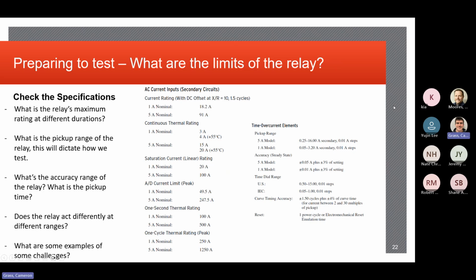Looking in the manual as well, you're going to be able to dictate what the limits of the relay are. Going back to Brian's point earlier when he was talking about burning up test plugs and whatnot. It's one thing to burn up a test plug in the field. That costs a couple cents. It's another to burn up the relay itself when you're doing your testing. That costs thousands of dollars. That goes directly back to the client, who will be extremely unhappy to find out that would happen. So testing your elements is great.